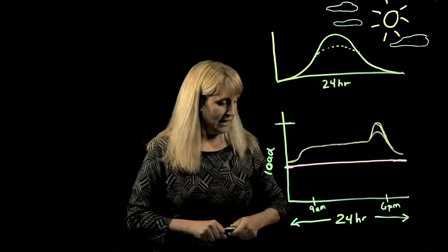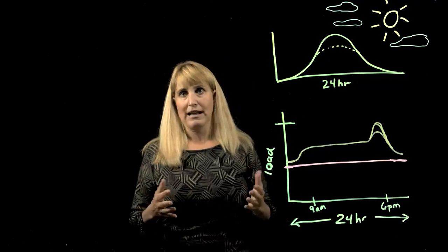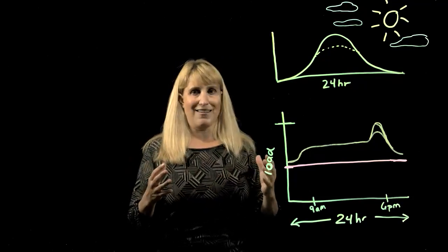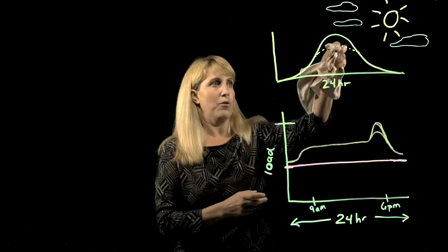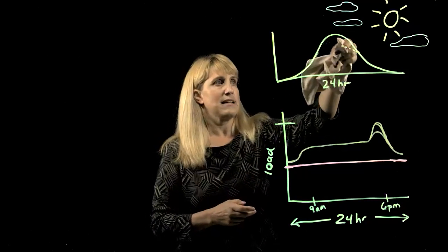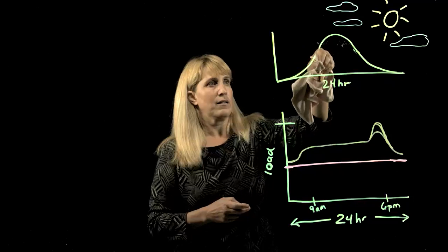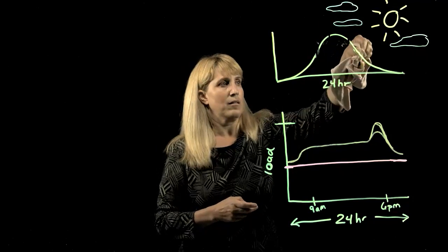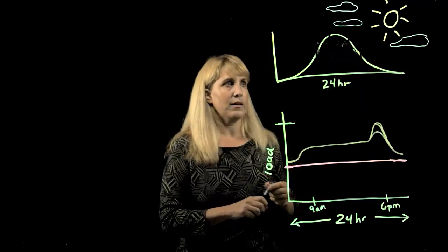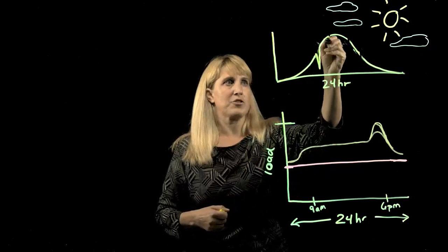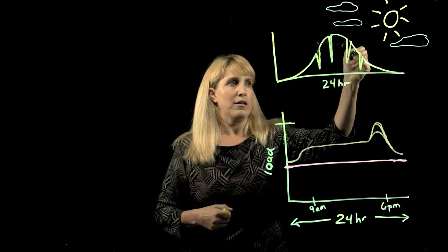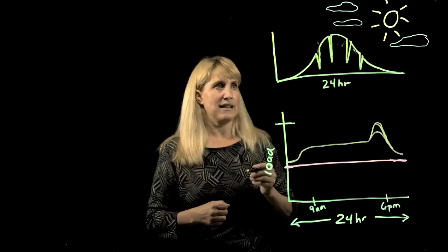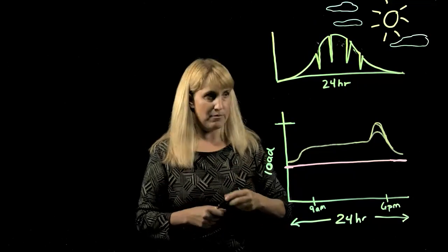But you might see sort of an aggregated decrease in the solar output across a particular generation profile for a day. On the other hand, if you have a small grid, a microgrid, that's in a pretty small geographic area, those sorts of events like momentary cloud cover are going to have a different impact on your grid output. So what you might see in that case is some pretty discrete dips in terms of the output from those solar panels when you're seeing that variable cloud cover impact the resource.